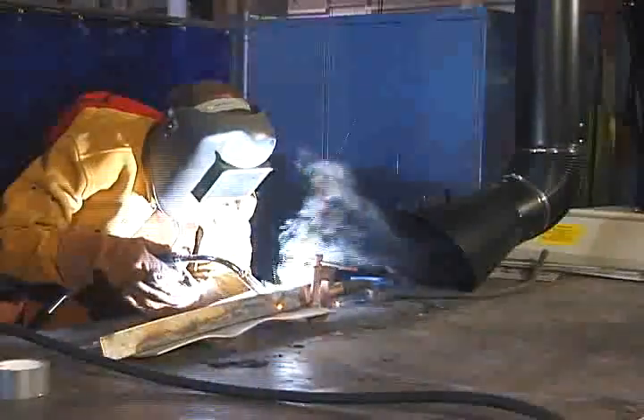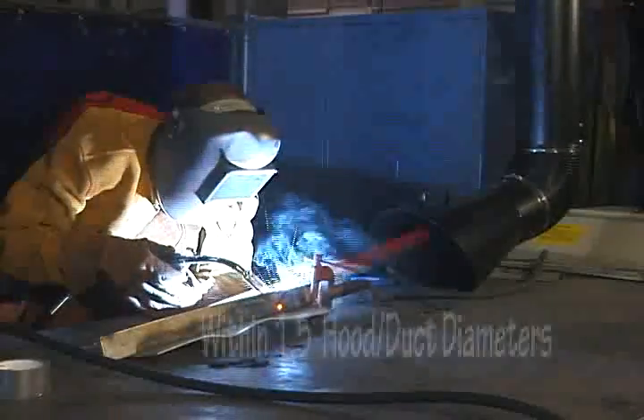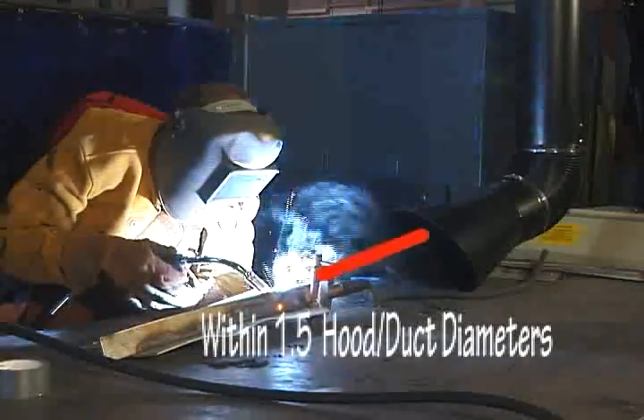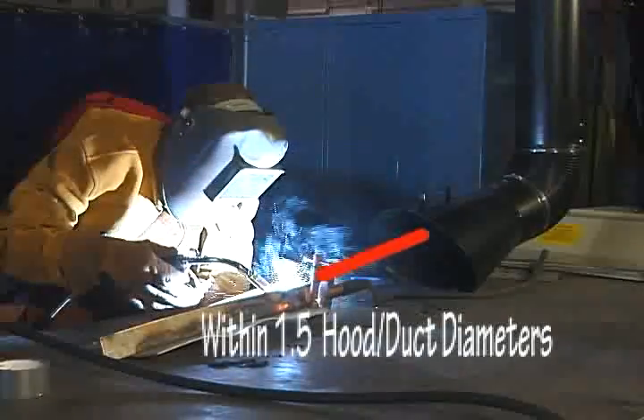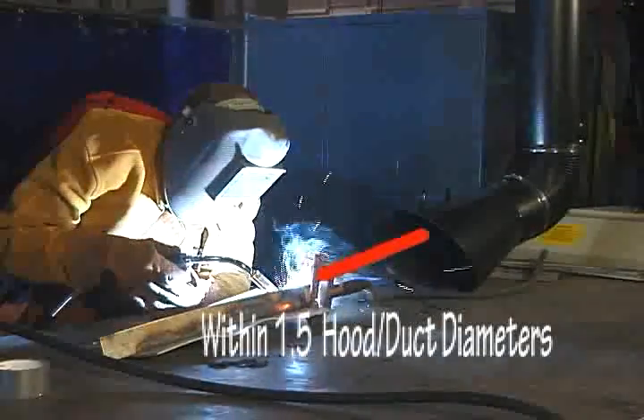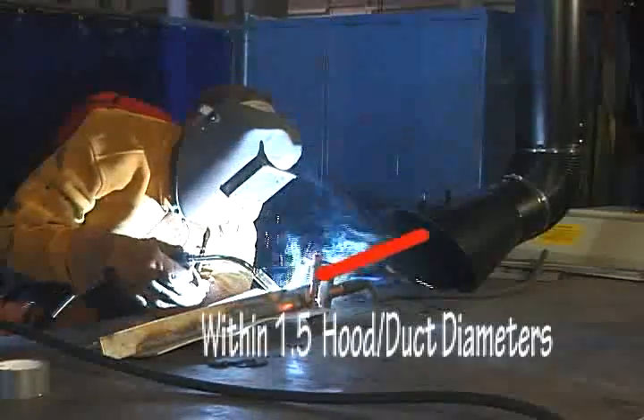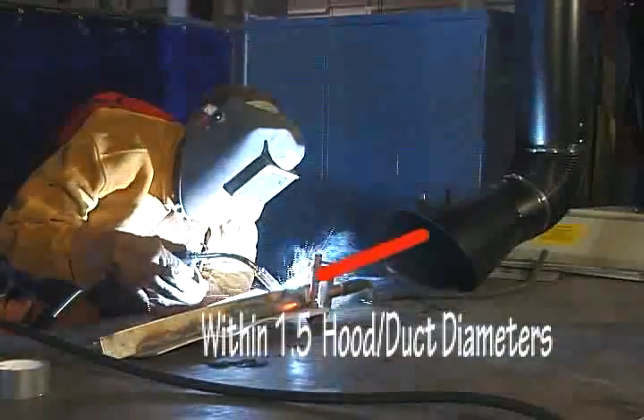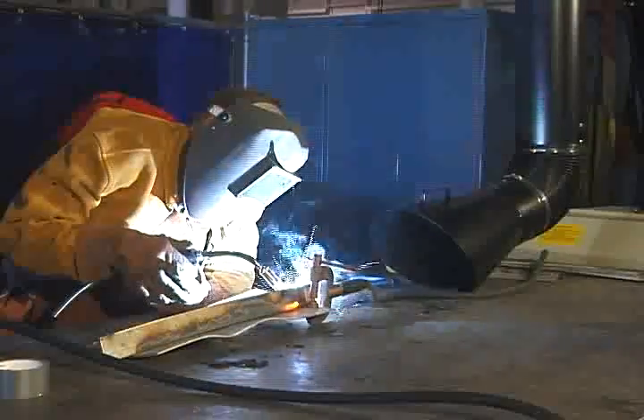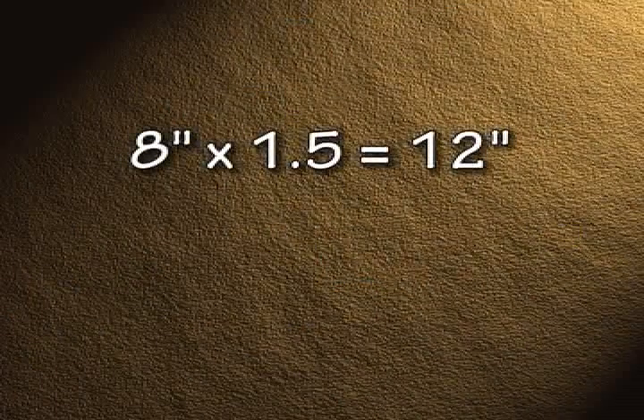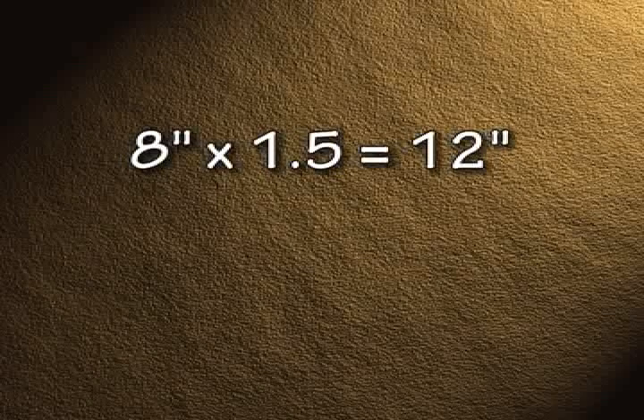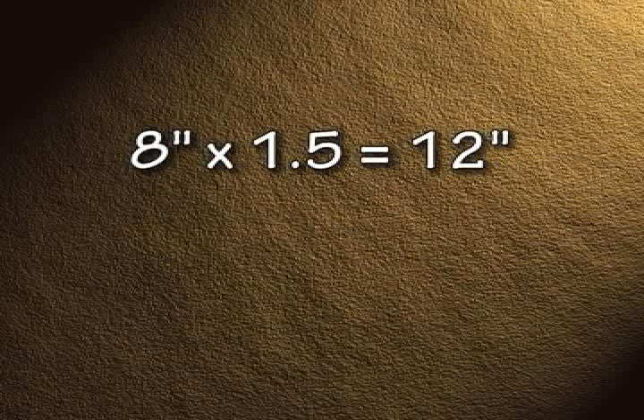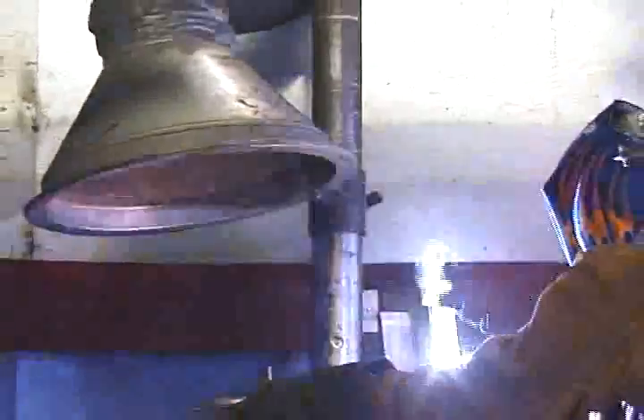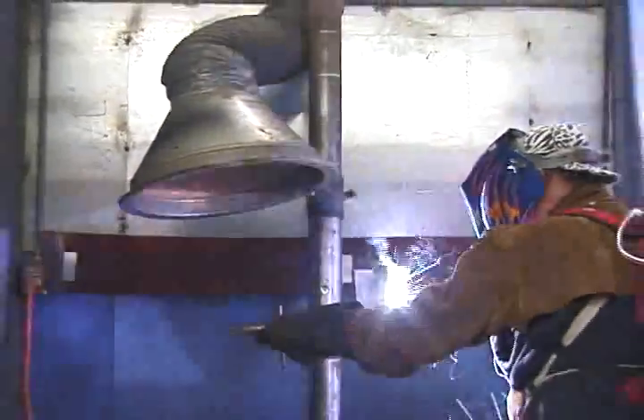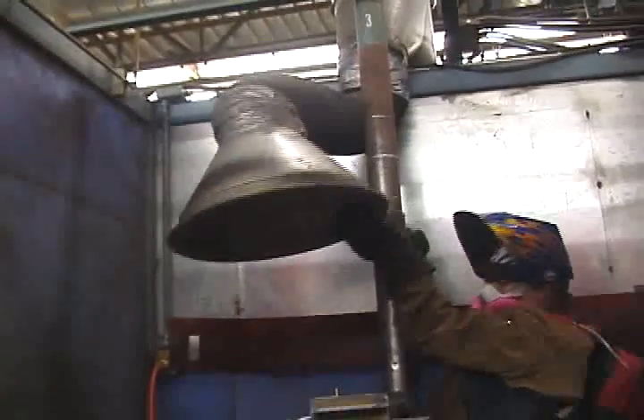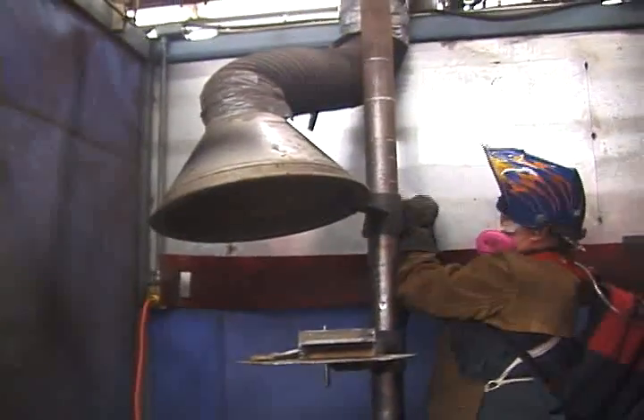The best way to maintain a capture velocity of 100 feet per minute is to position the LEV hood within 1.5 hood or duct diameters from the source. Use duct diameters if you don't have a hood attached to the ducting. Otherwise, use the diameter of the hood if it's a sphere, or the longest side if it's a rectangle. For example, if you have an 8-inch diameter round hood opening, the hood should be positioned 12 inches from the arc. If you're working on a large part, keeping the hood at 1.5 hood diameters from the weld will require that you frequently check the position of the hood and readjust its location.